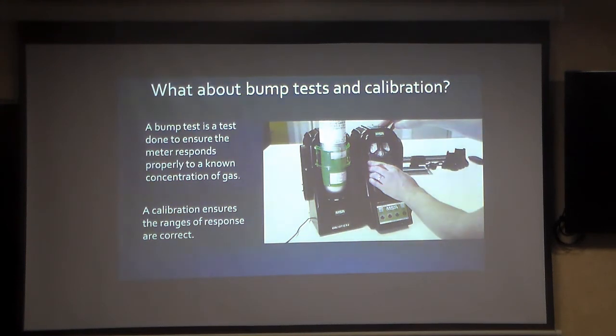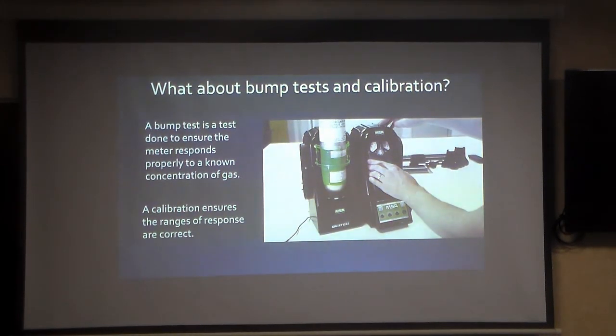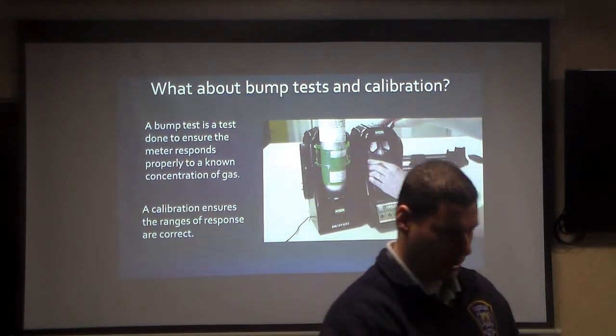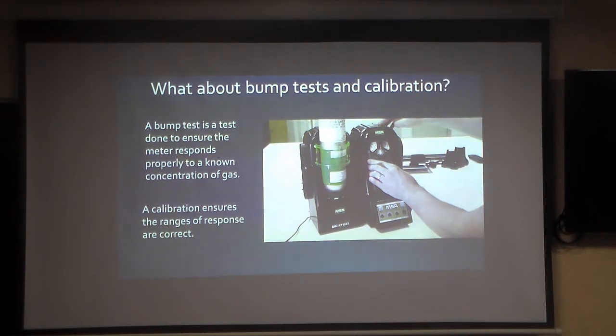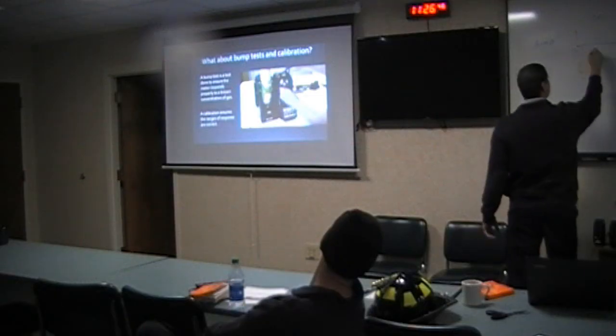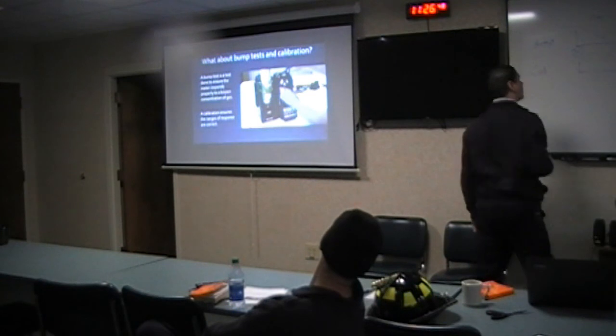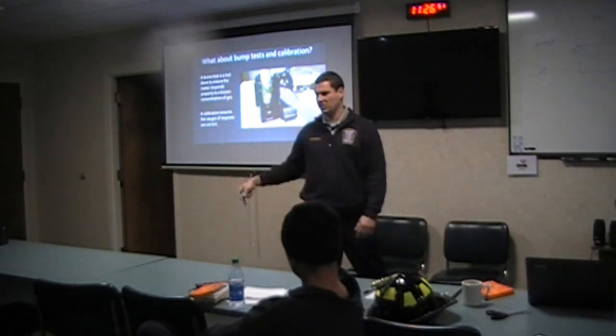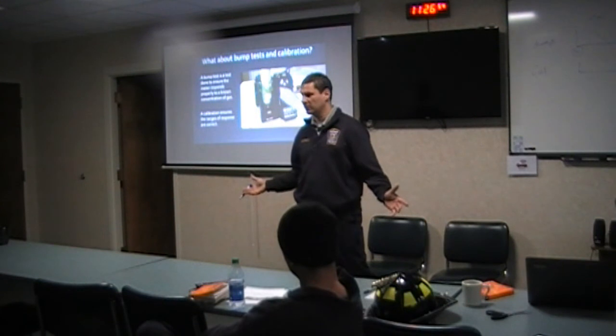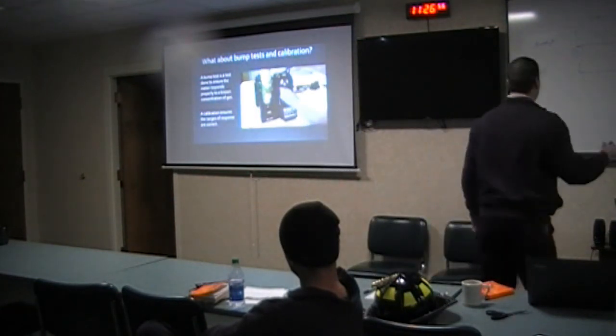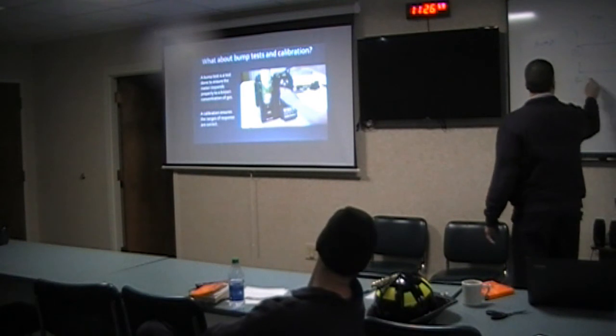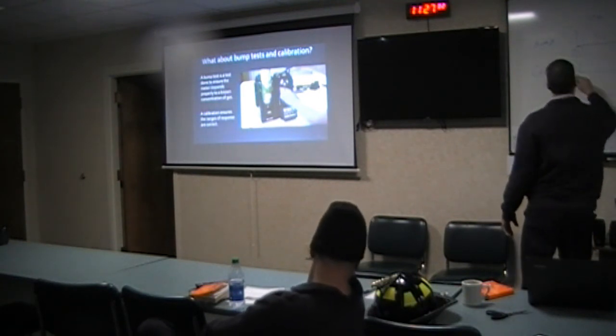Let's just make something up, I'm trying to remember what the CO numbers are. So what a bump test does is, before you leave to go on a call, you put the meter inside this machine, and it sends a reading of CO in this range to test it, to make sure it's working properly. It does that for all the sensors, just to confirm everything's working, and it takes about 15 seconds. Calibration, on the other hand, is done to make sure these numbers are correct.